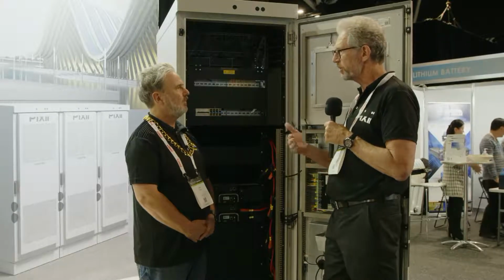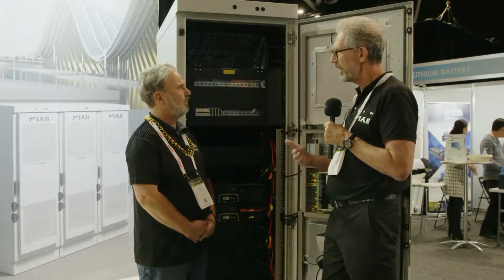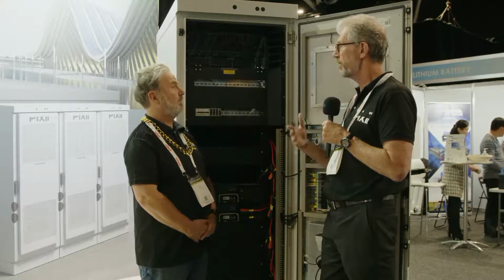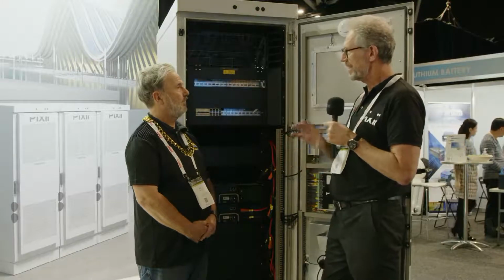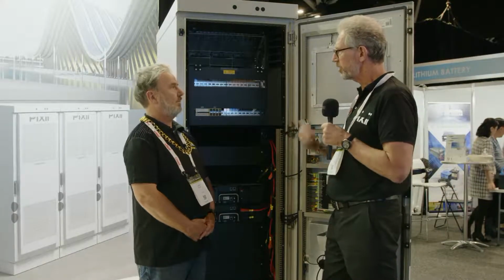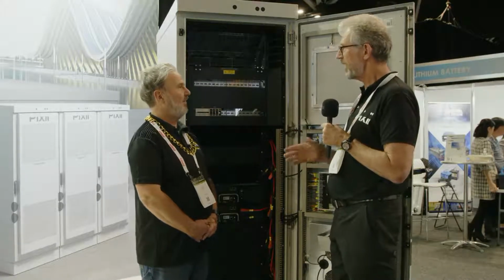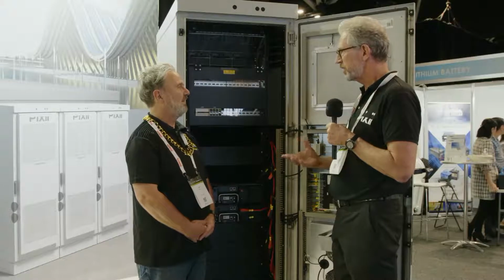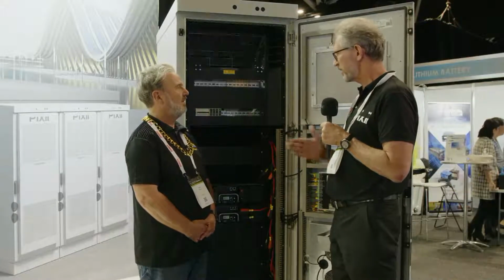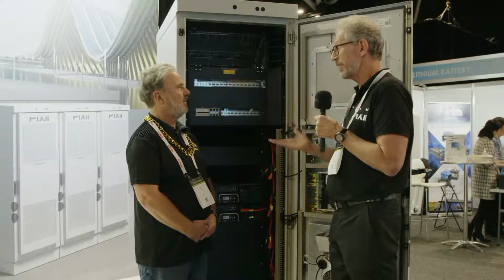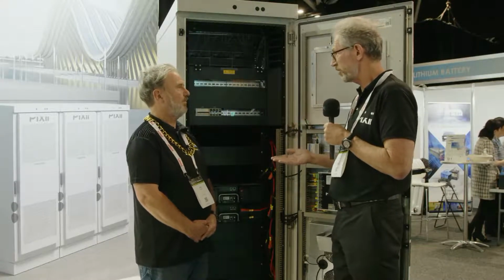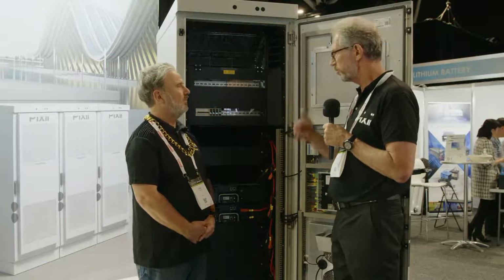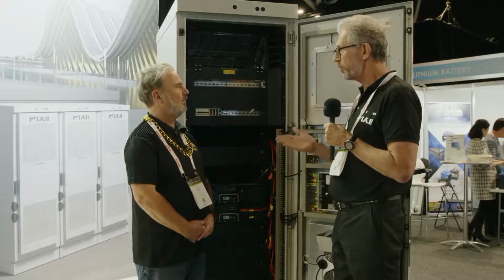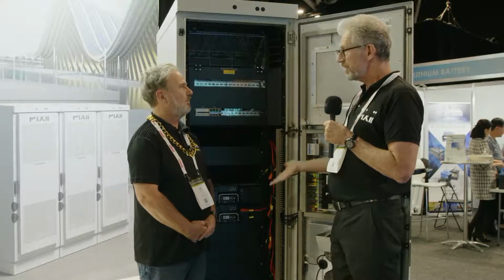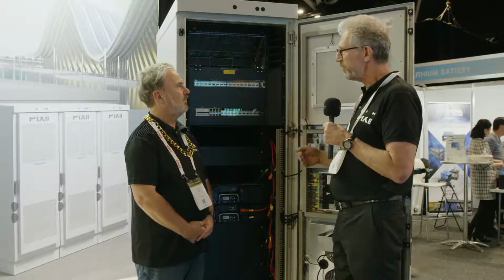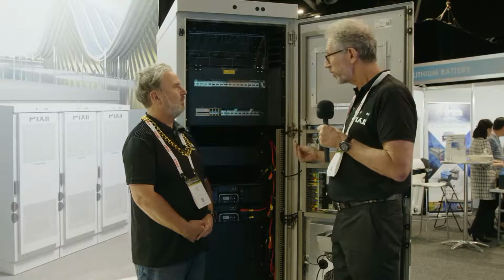The module itself is also software configurable, so we can make it into an MPPT module at the same time — both an MPPT module and a battery inverter in the same system, using the same module, just reconfigured in software. That gives us a 48 volt DC coupled hybrid system that can scale from 3.3 kilowatts. In a domestic application it might be 10 kilowatts of battery storage and 10 kilowatts of MPPT from the roof, scaling upward to 50 kilowatts in a system like this, and then master-slaved up to a megawatt or more.